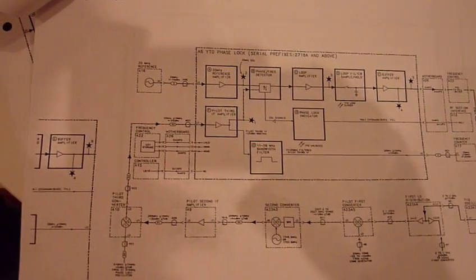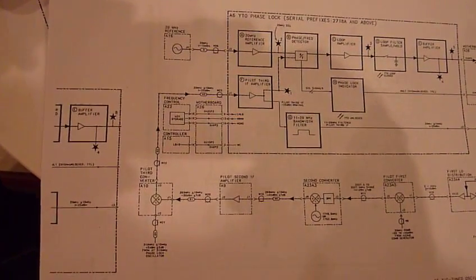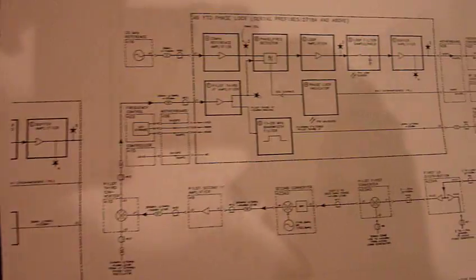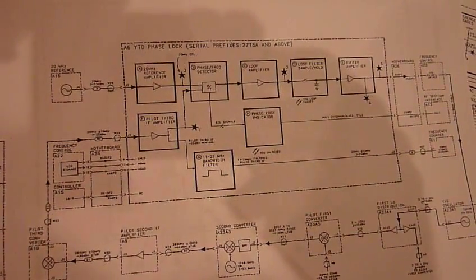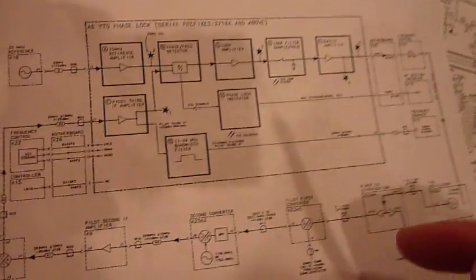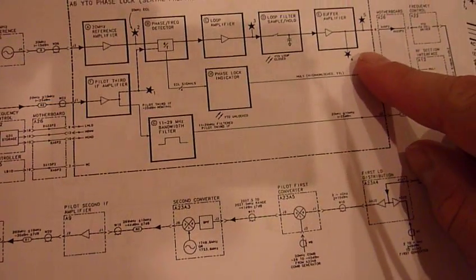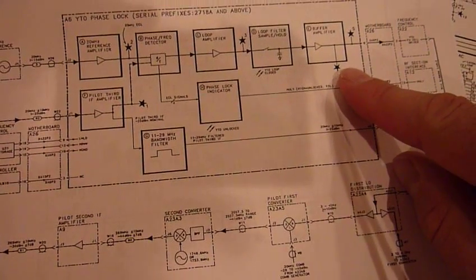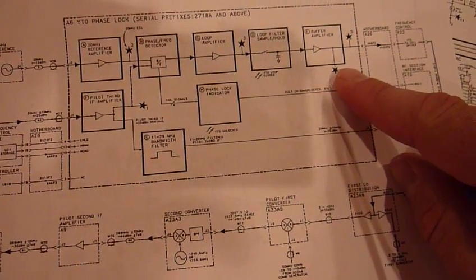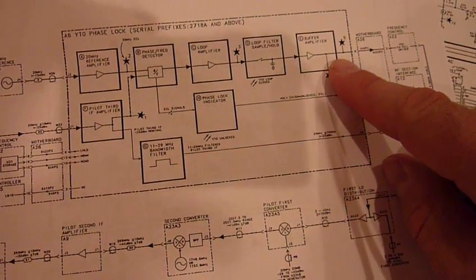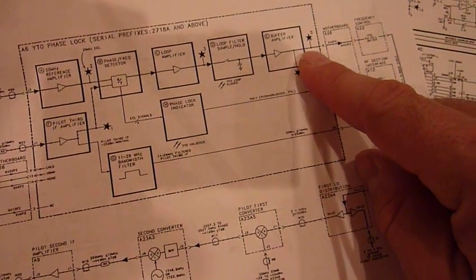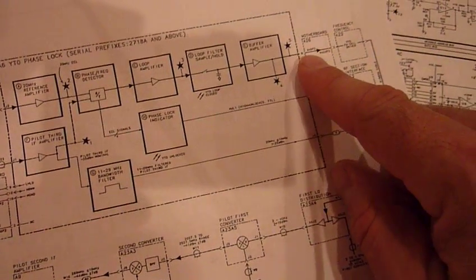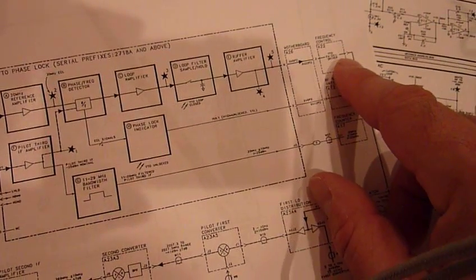So somewhere inside here, this is the board A6, that's the phase lock loop. I realized there was a test point I could look at which is the output of the phase lock loop that goes into the frequency control unit.